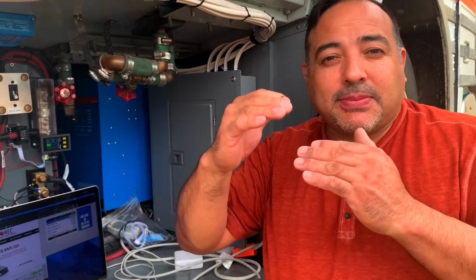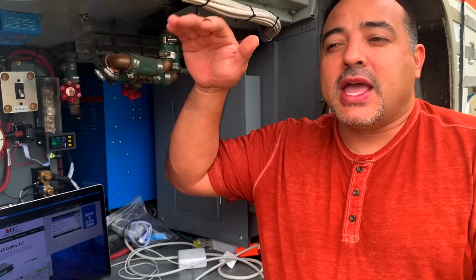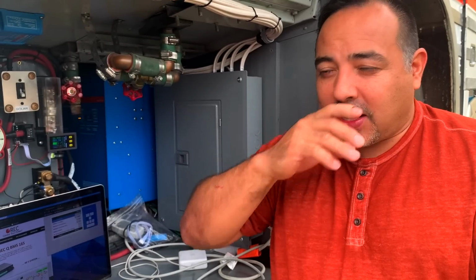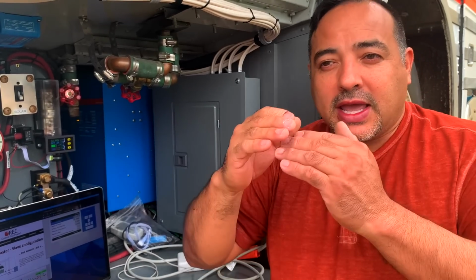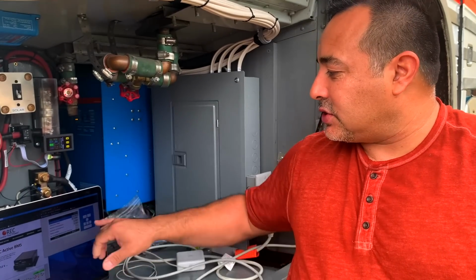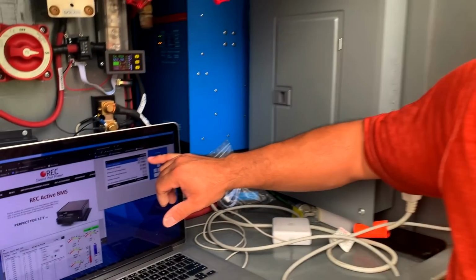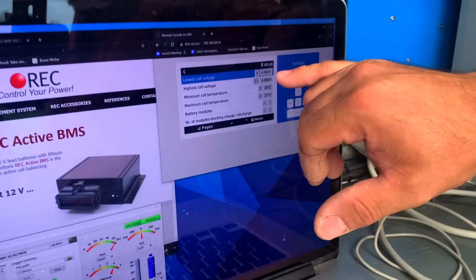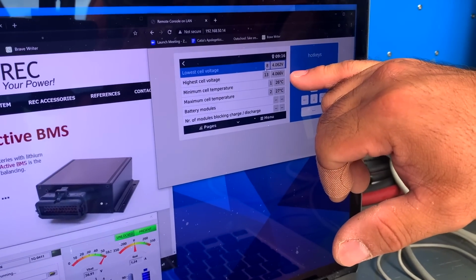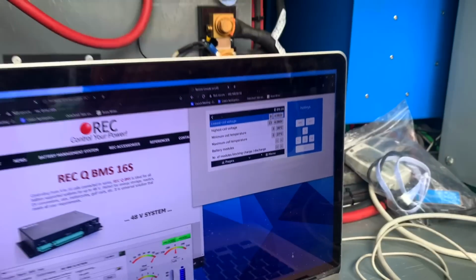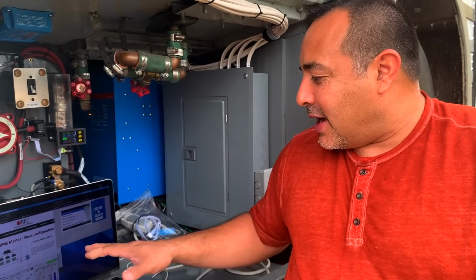What we did do is keep a tally on the voltage drift between the highest and lowest cell as it went all the way down and came back up. As it went lower and lower, it started to drift apart a bit more, but nothing outside of our safety parameters. Now that it's charged back up, we see a minimum cell voltage of 4.062 and a maximum of 4.066, so our voltage is only off by 0.004 volts, which is pretty perfectly balanced.